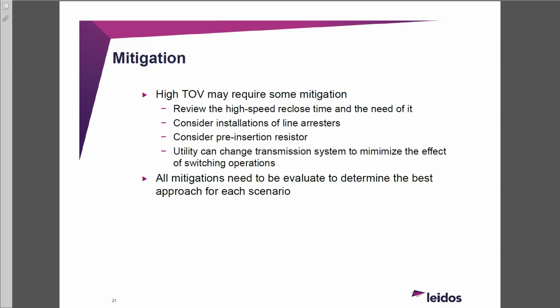To your point, if a lot of these situations are post-fault inspections, what you said about assuming there are no arresters on the line—well, what if some percentage of them are compromised, or the insulation is somewhat compromised because that was the genesis of the fault to begin with? A study like this really helps with capital projects. It's one of those things where we show this, they have issues, and they can add it to next year's project list.